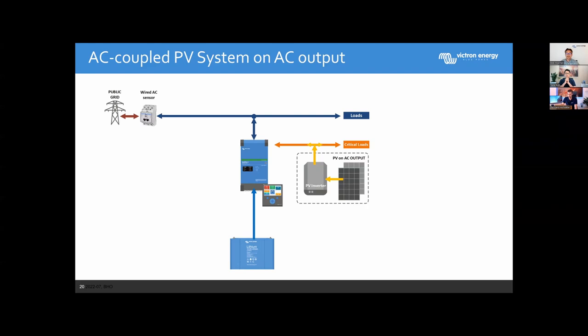Because there is no actual grid, the system runs in island mode. When the battery reaches 100% state of charge, the output frequency is increased — this is called a frequency shift, a parameter that can be set in configuration. Today we will see that this frequency shift is also used for sector coupling with heat — that is what we'll see with MyPV.